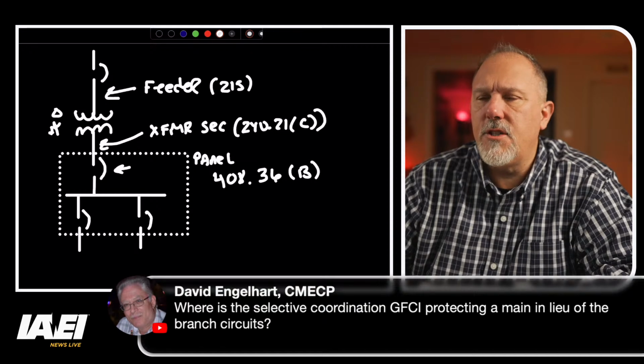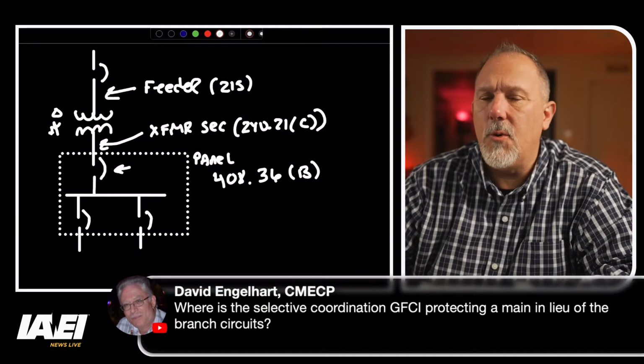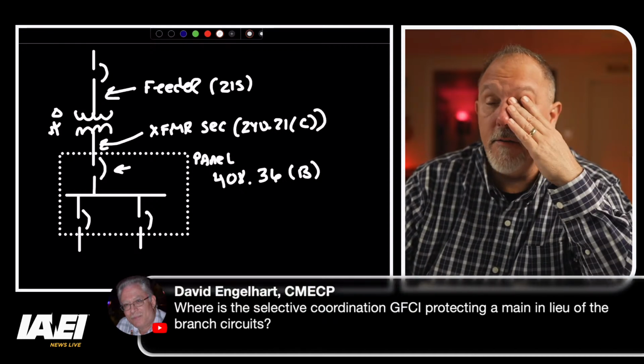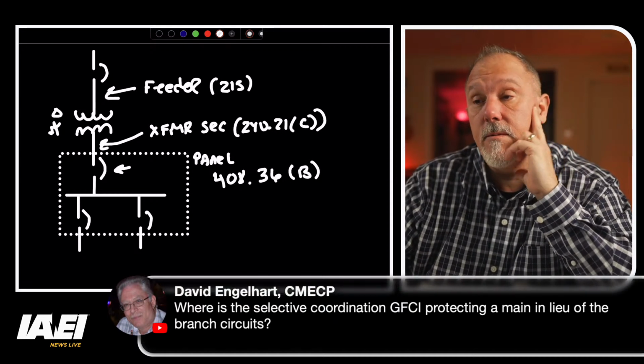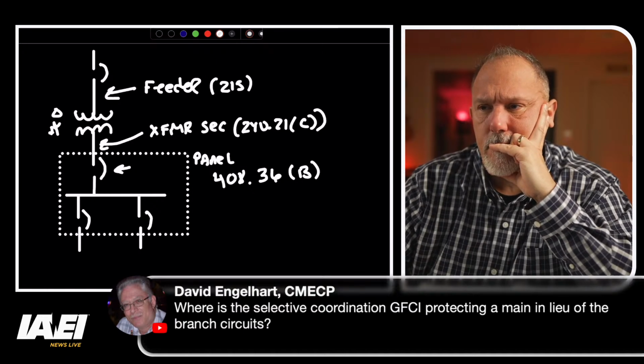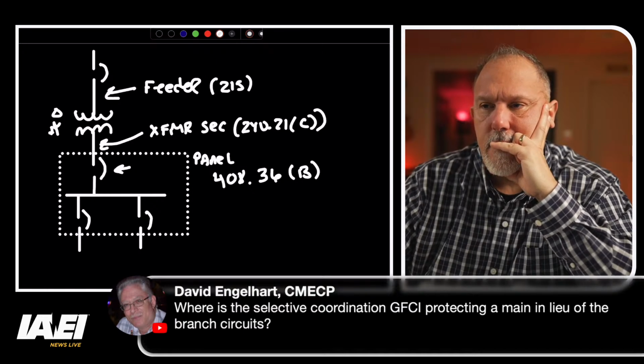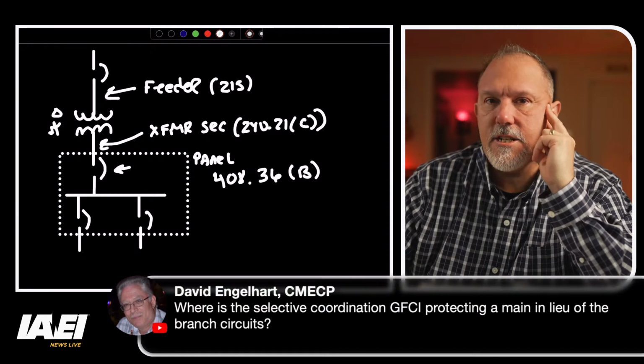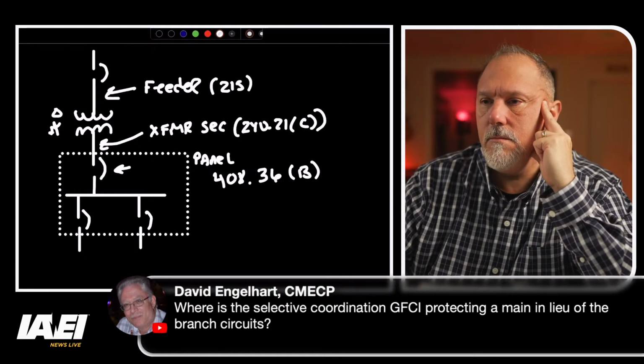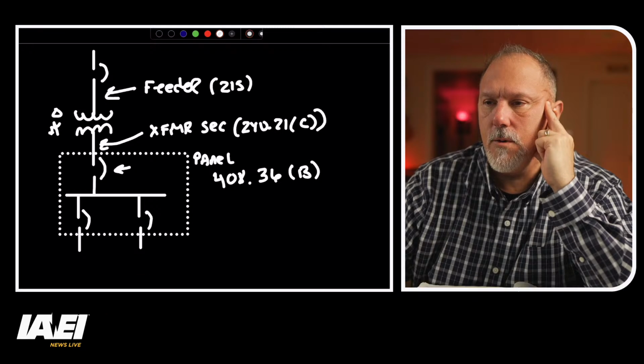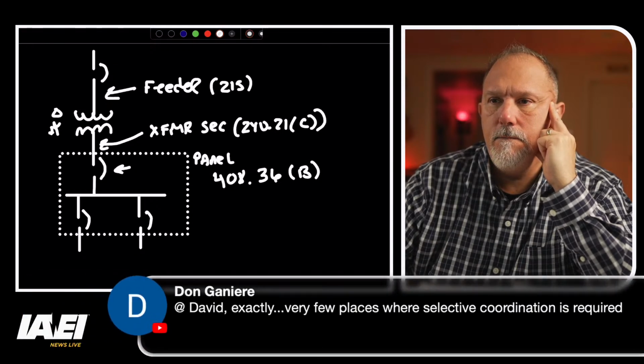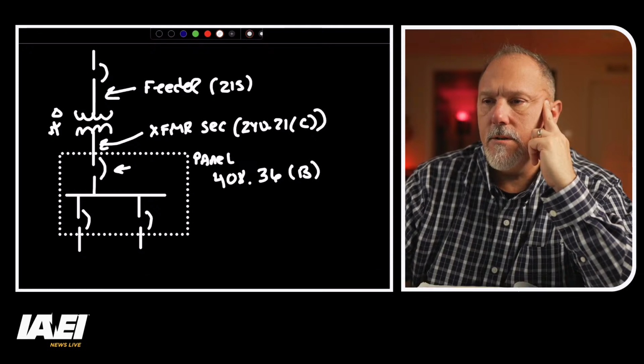You have selective coordination requirements in 700, 701, 708, and in a few other areas, not in healthcare. 517 does not have a selective coordination requirement. But that's the challenge. That is a challenge for us. Very few places where selective coordination is required, David, exactly. Very few.